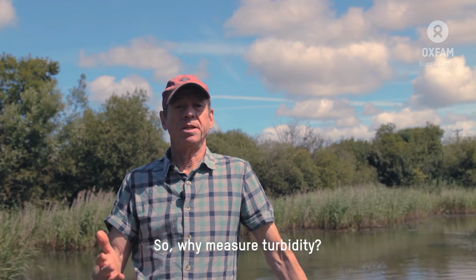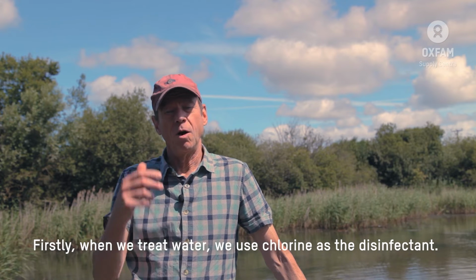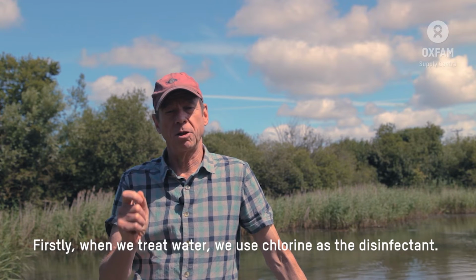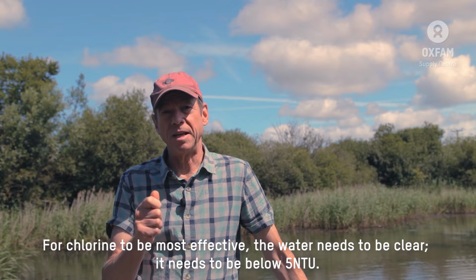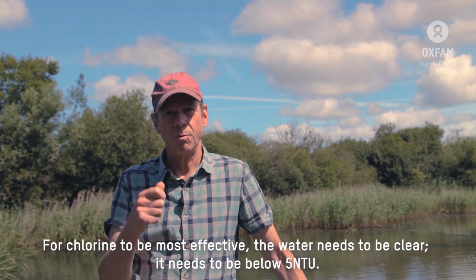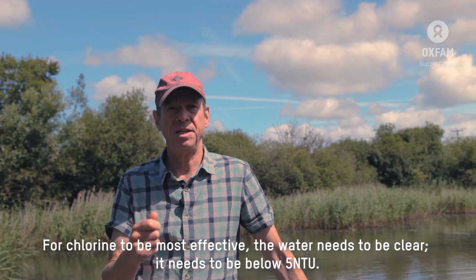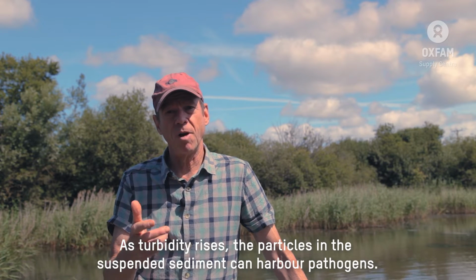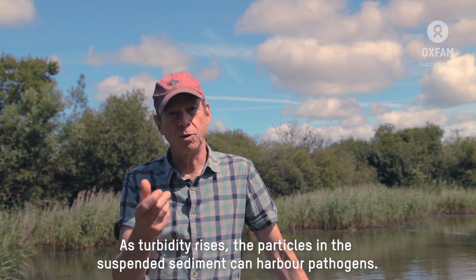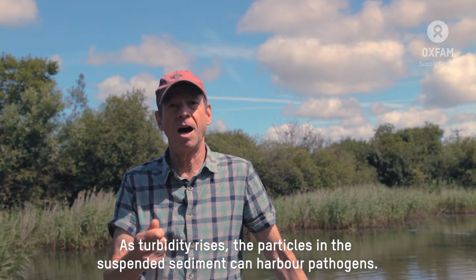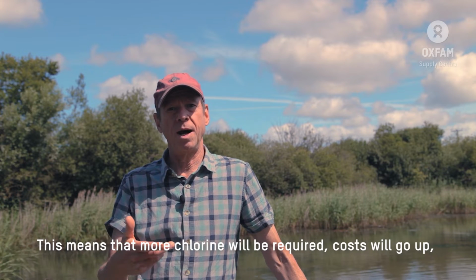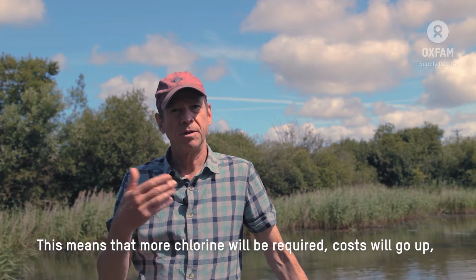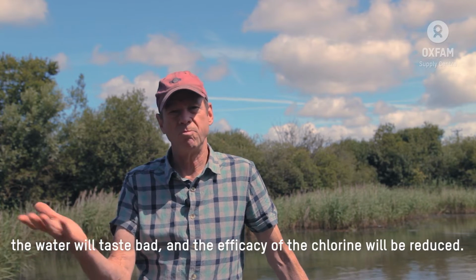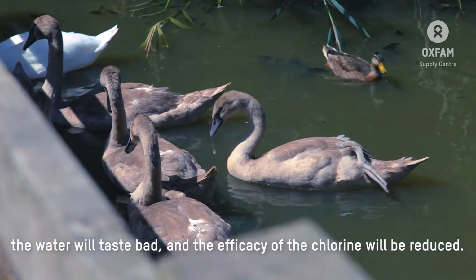So why measure turbidity? Firstly, when we're treating water, we're going to be using chlorine as the disinfectant. For chlorine to be most effective, the water needs to be clear. It needs to be below 5 NTU. As turbidity rises, the particles and the suspended sediment can harbour pathogens. This means that more chlorine will be required, the costs will go up, the flavour of the water will be made bad, and the efficacy of the chlorine is reduced.